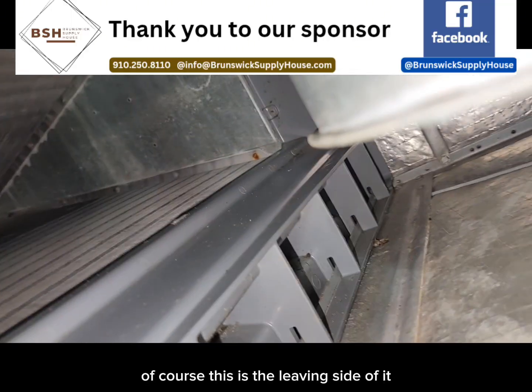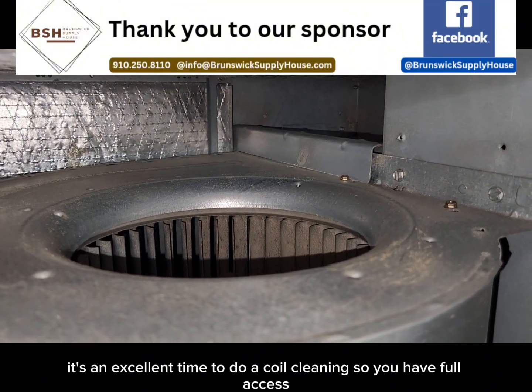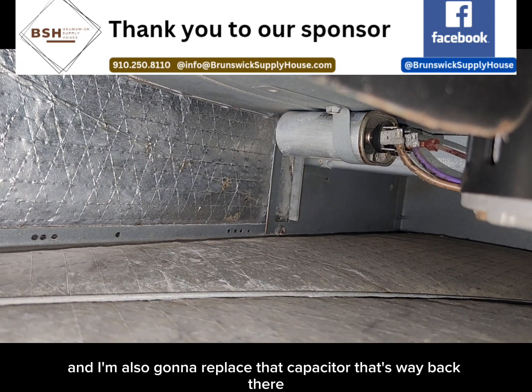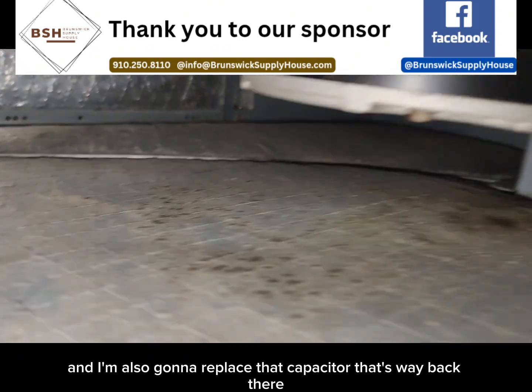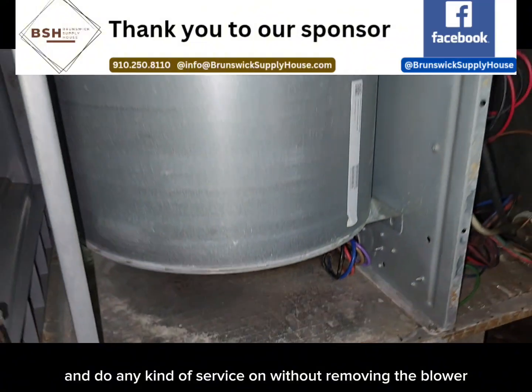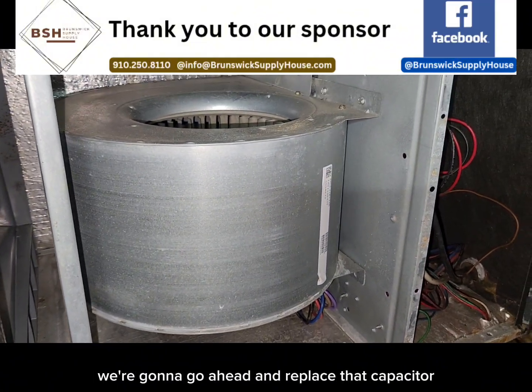It doesn't look too bad — of course, this is the leaving side of it — but while I've got the blower pulled out, it's an excellent time to do a coil cleaning so you have full access. And I'm also going to replace that capacitor that's way back there, that's really hard to test and do any kind of service on without removing the blower. So if we're going to pull the blower wheel out, we're going to go ahead and replace that capacitor.